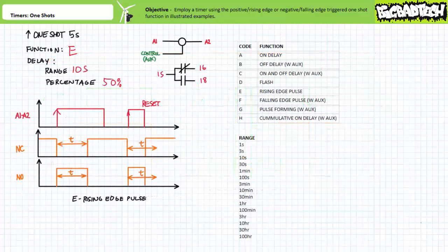As previously, if the timer ever lost power during an ongoing one-shot, the ongoing one-shot would be canceled and reset, and all associated contacts would immediately return to the deactivated state. The restoration of power returns the timer to service. To set up a multifunction timer to execute the one-shot function, the technician must first choose the correct function and then set the delay period.